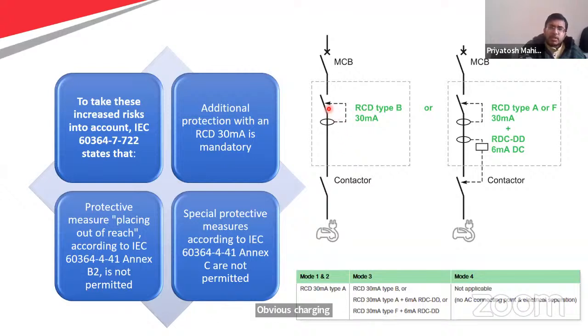Now you see here, first we have connected RCD type B, which is allowing 30 milliampere maximum current. If the current is more than this, it will detect a fault or any abnormal situation and it will open, so that this device will be protected.